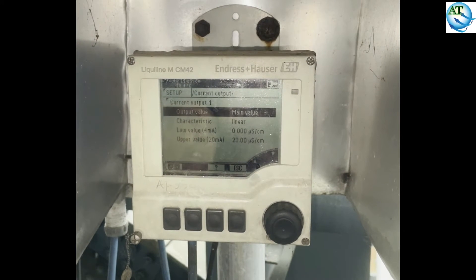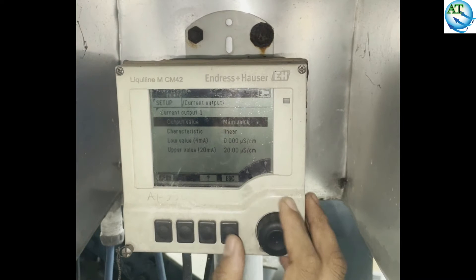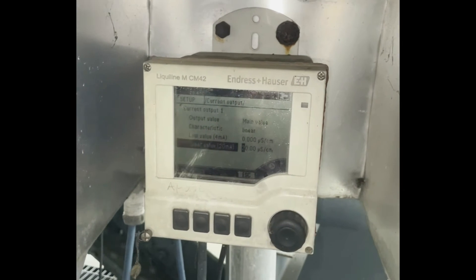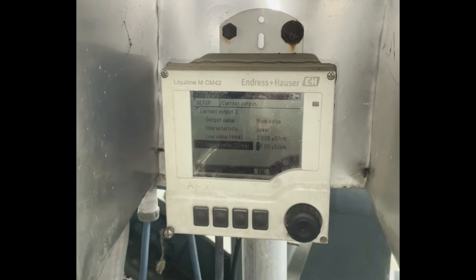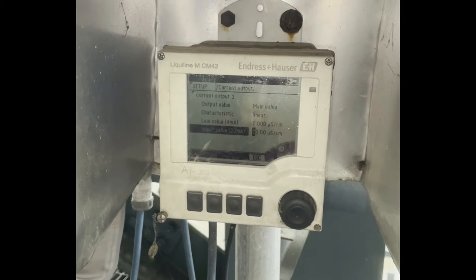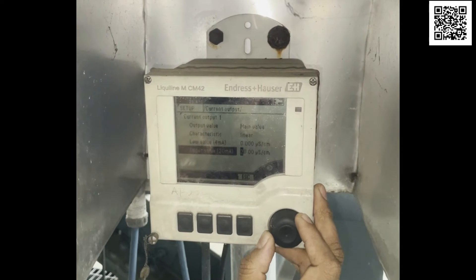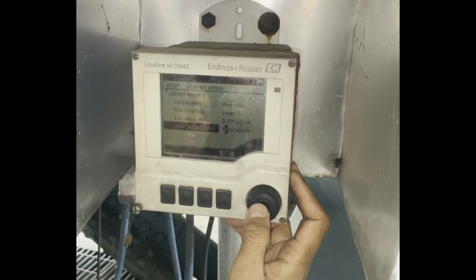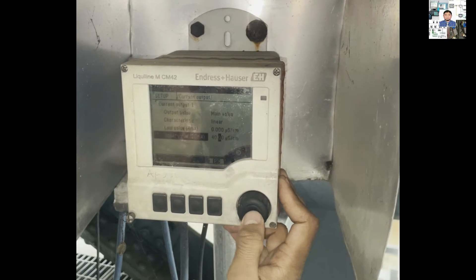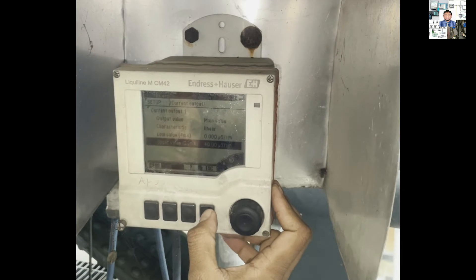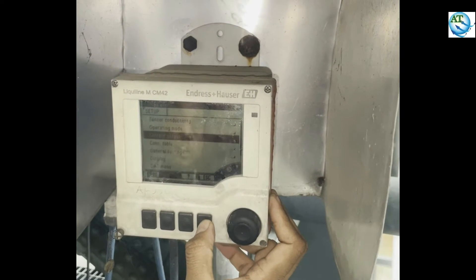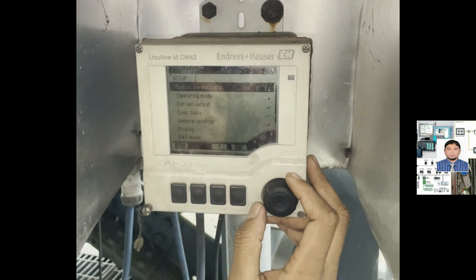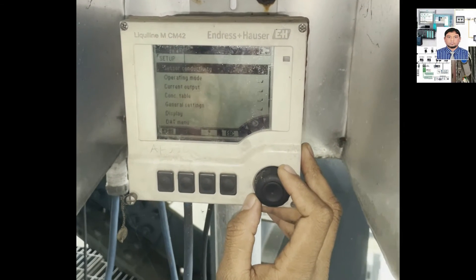The upper value is the maximum value that you want to measure, and the lower value is almost 0. You can change the upper value to measure different range values or calibrated values. Currently the transmitter is showing 0 to 20, and now I change it to 0 to 40. After changing, you press the enter button — when you rotate the knob and press the middle position of the right side knob, you can enter edit mode and change the different values of this transmitter.